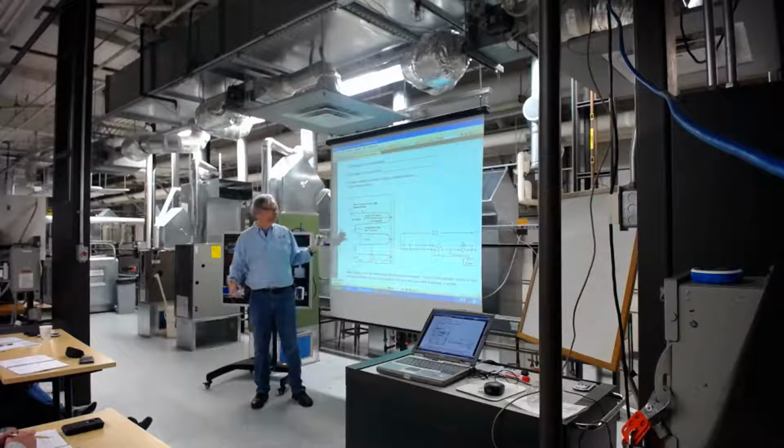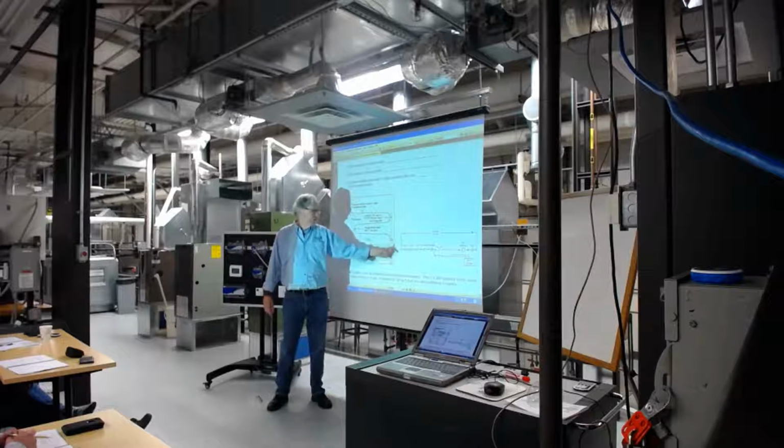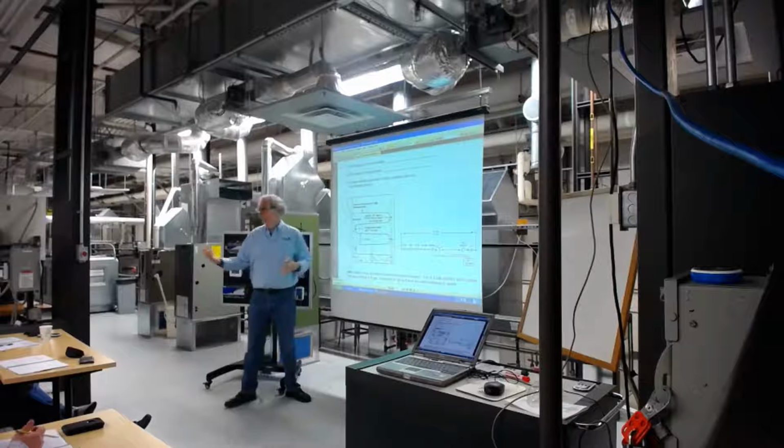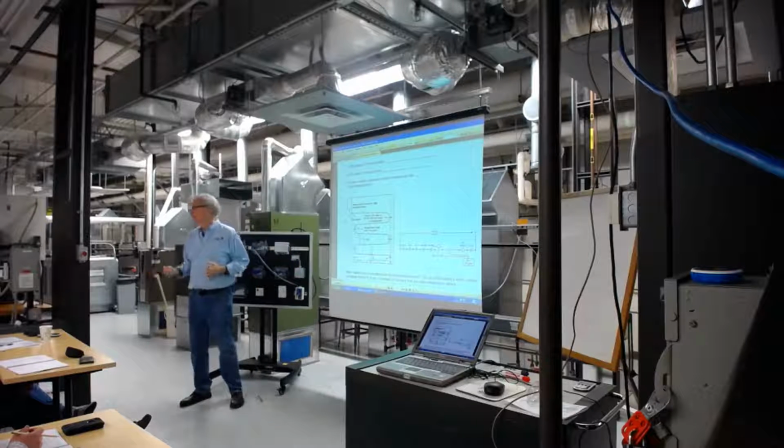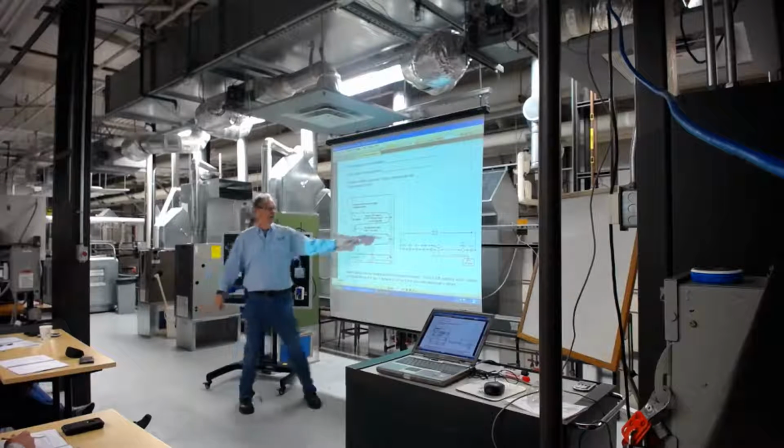That's the first thing. The other thing to do is then power up the unit. You come out now, take off your meter, and power up. Right on this little box there's a little override switch that you kill when you open up those contacts manually. Then you can push that. Now you're verifying that the electrician did their job.